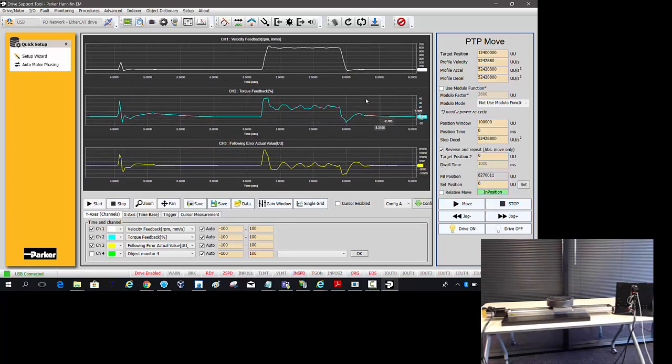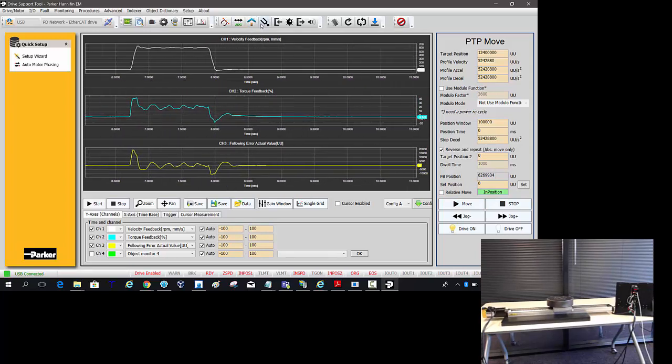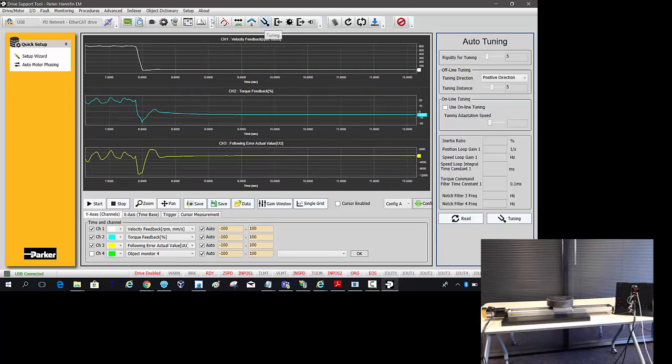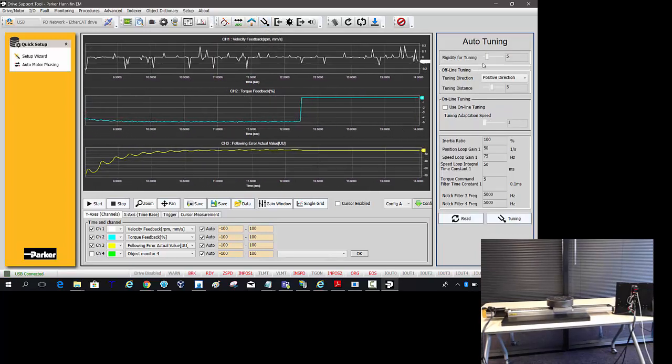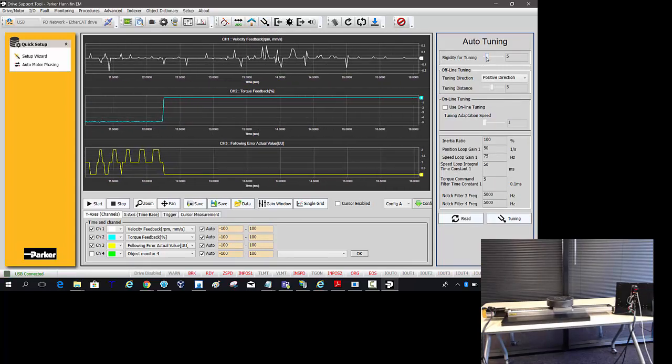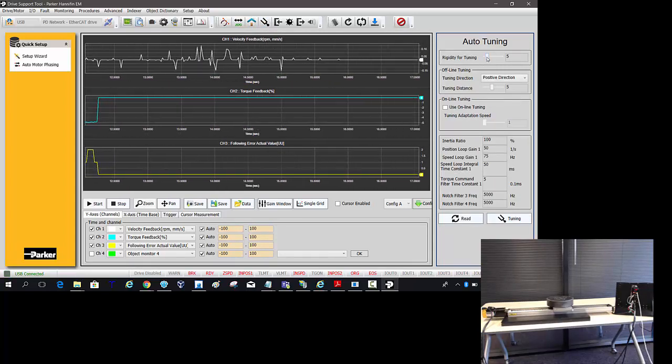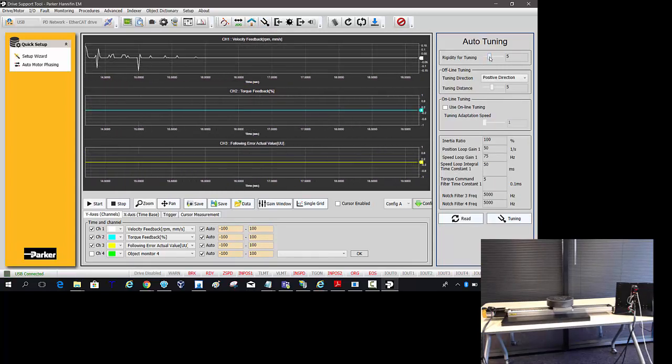I'm going to stop it in the middle of the travel. If we go into the tuning, the rigidity is a relative number. If we increase this, and typically what I want to do is increase it, put the actuator in the middle of the travel.